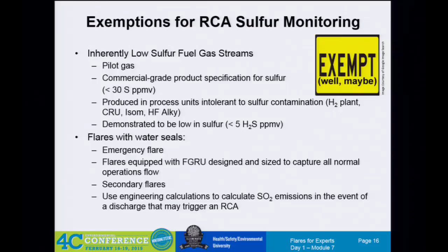There are also exemptions for flares that have water seals. In that case you don't have to do the sulfur monitoring, but you do have to monitor the water seal itself — water level indication and pressure in the header — to know when you've broken through the seal. Once the pressure in the header exceeds the pressure held by the water seal, that's considered an event, and then you have to estimate your sulfur emissions.